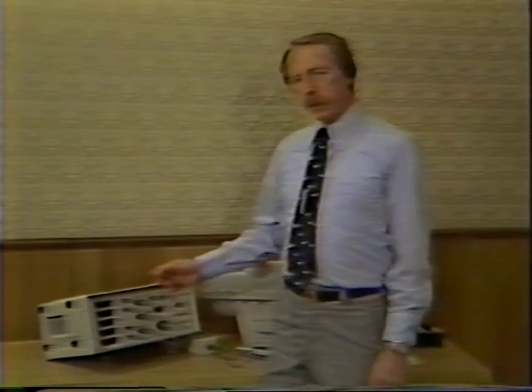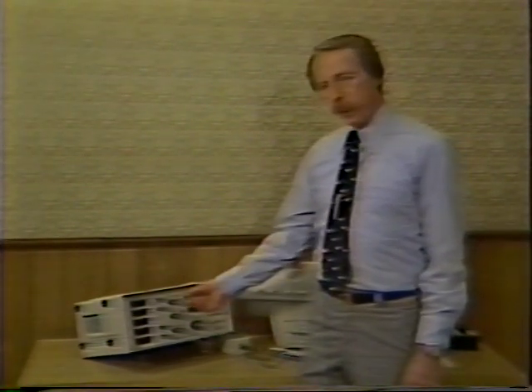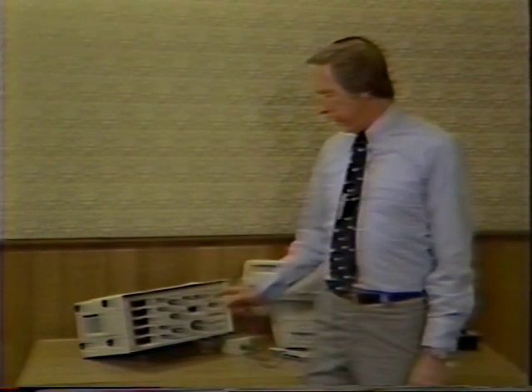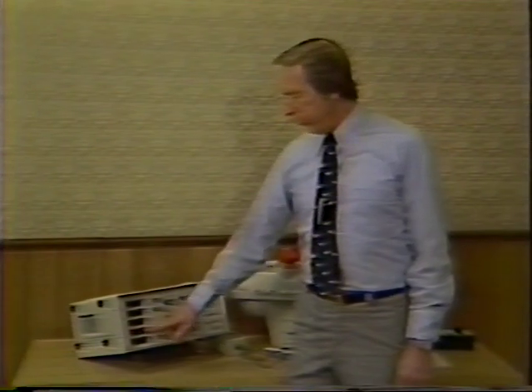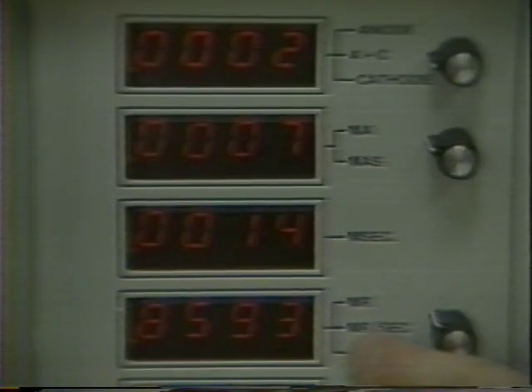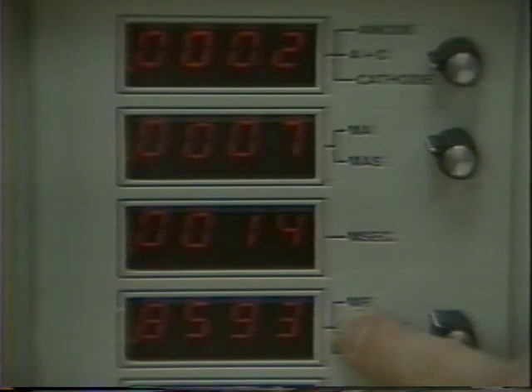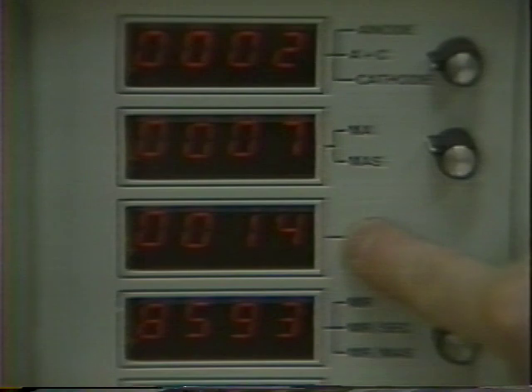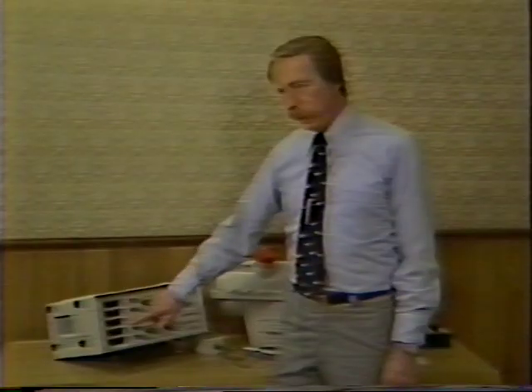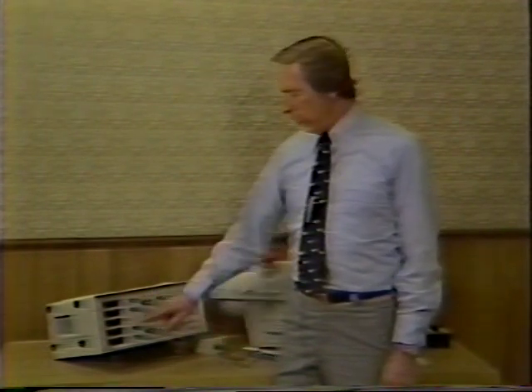We now have 10 exposures in the memory. In order to do the coefficient of variation calculation, we switch the procedure switch to the coefficient of variation position. At this point, on the 4th LED, or the radiation display, we will be able to read the calculation of coefficient of variation of radiation as required by the BRH. If we have a problem there, that problem is no doubt derived from one of the other 3 parameters, time, MA, and KV. Thus, we have done a coefficient of variation calculation on that data also.